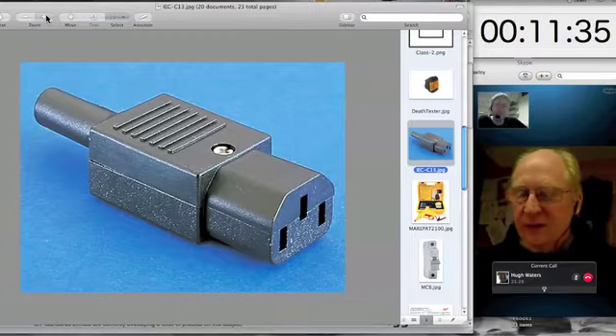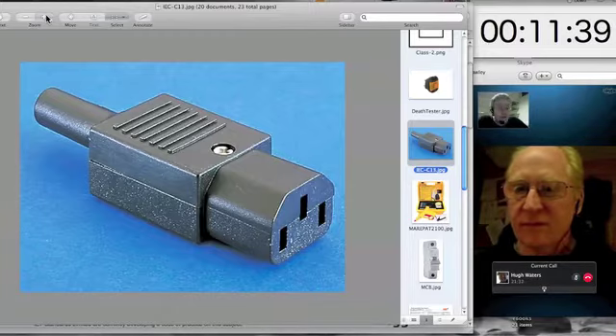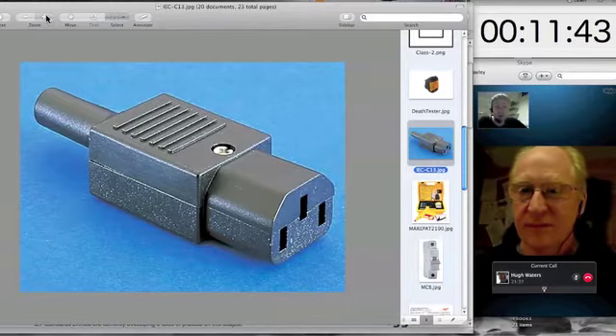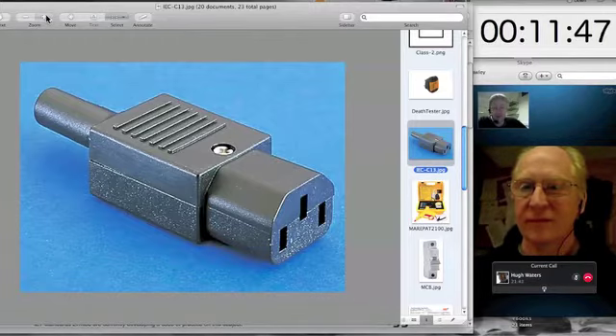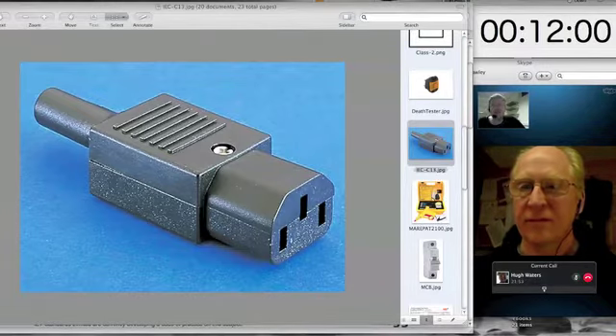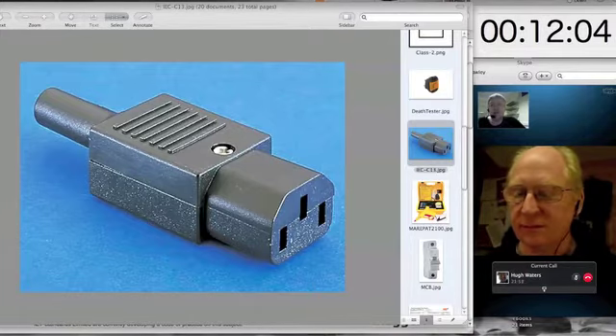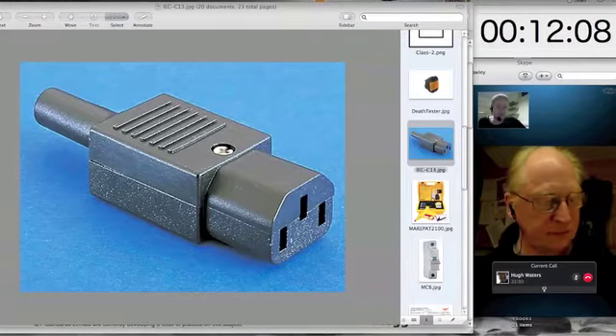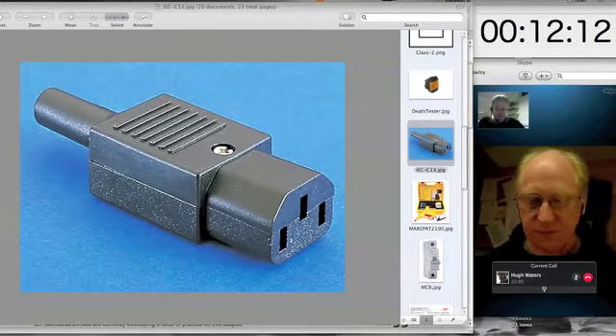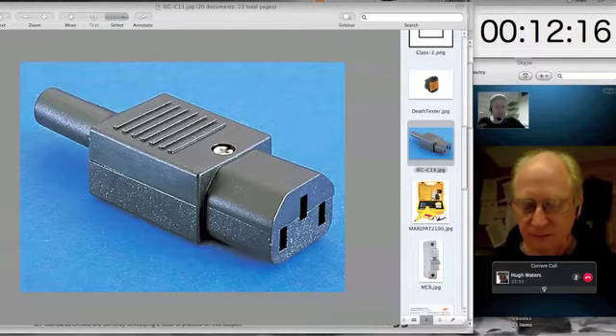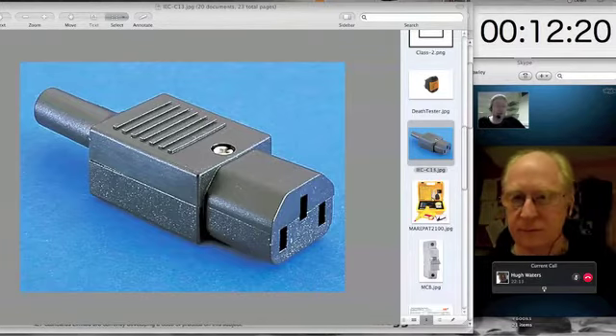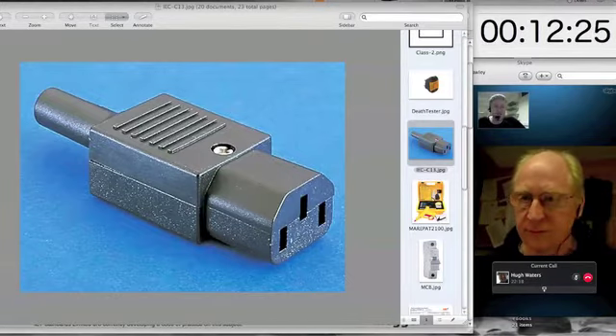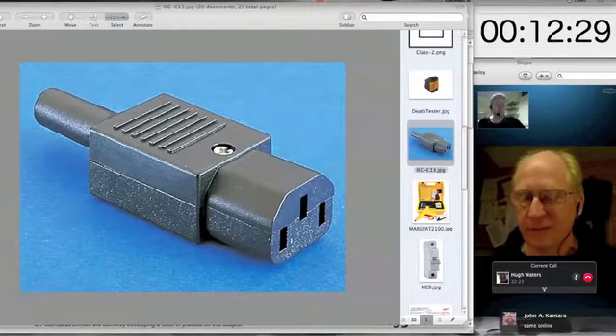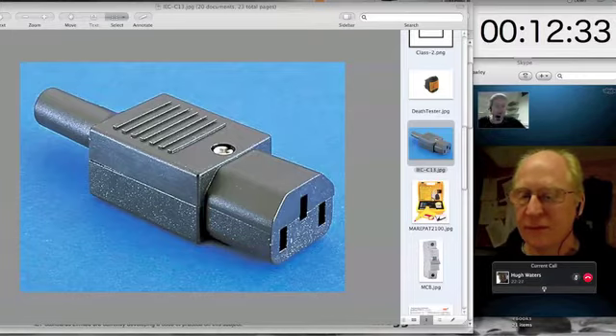So that's fuses. Now, a fuse really satisfies two functions. If a piece of equipment were to develop a fault and start dragging an awful lot of current, which could cause cabling to burn out and things like that, and a fire hazard, the fuse will blow, thus rendering the equipment safe. Or, more importantly, the fuse also works in conjunction with the other great safety feature that all mains powered equipment has, and that's the earth. The earth is that connection that will essentially, if the metal box of the equipment should become live because of some internal fault, maybe the internal power supply, something has come adrift and a live connection has touched onto the metal box of the equipment, because the metal box of the equipment is also connected to this earth connection, that will sink as much current as the main supply can give it down to earth, and of course that causes the fuse to rupture. So the equipment is rendered safe, and hopefully nobody dies by touching what's now a live piece of equipment.